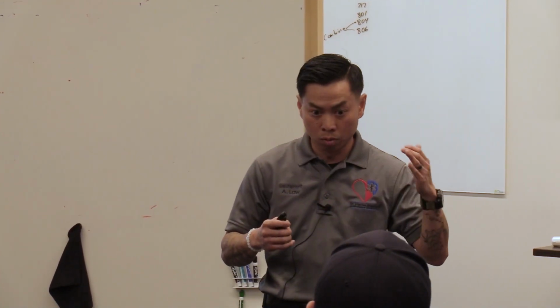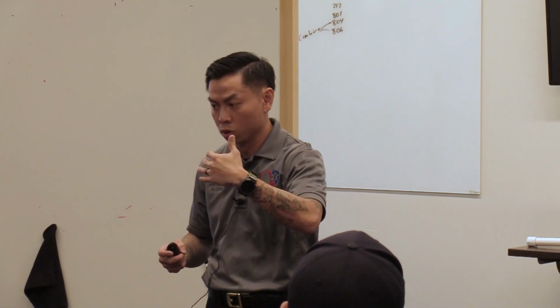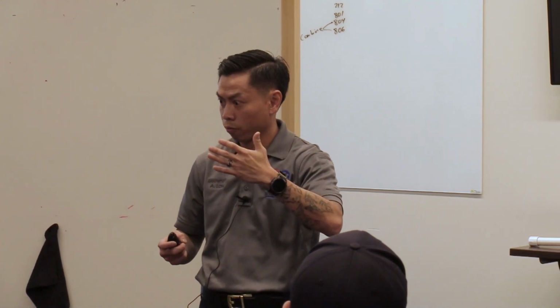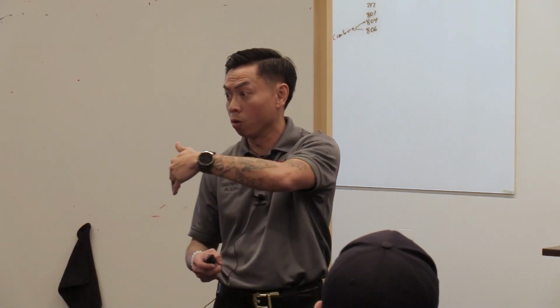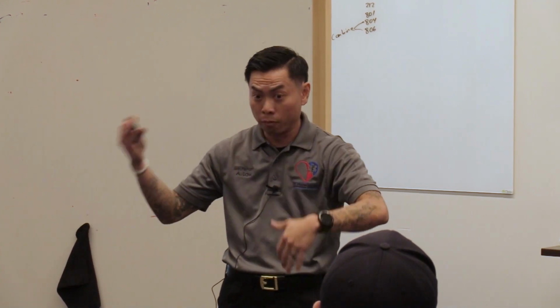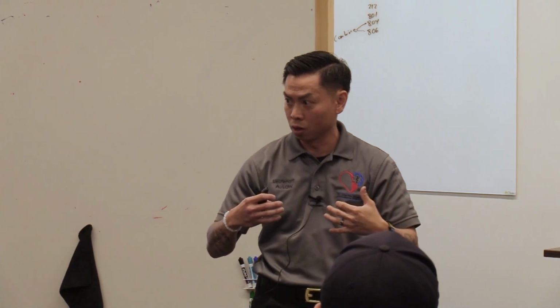Not to dog on the shift before you, but a lot can happen between when they test it and when you put it on a patient, right? They might have a crazy shift where the ventilator's thrown around in the back of the cabinet and something happens to the circuit. Then you try to use it on a patient four rotations later, and it's got a crack in it. Well, it might not be as simple as throwing a new circuit on. You'll have to do all that stuff. So now you saw how tedious it was, and you're delaying patient care on top of the stress of equipment failure. It's making it that much worse.